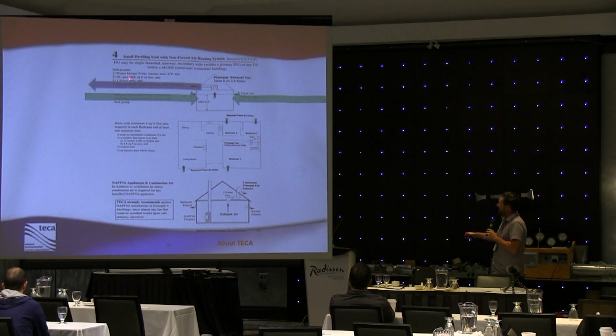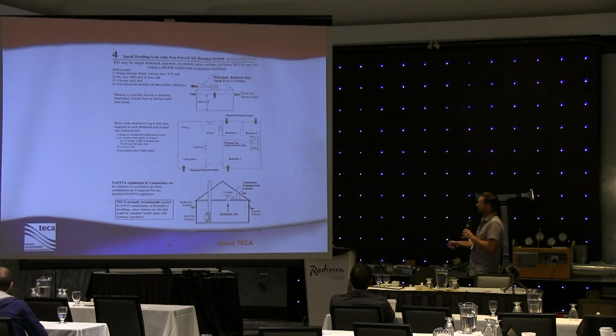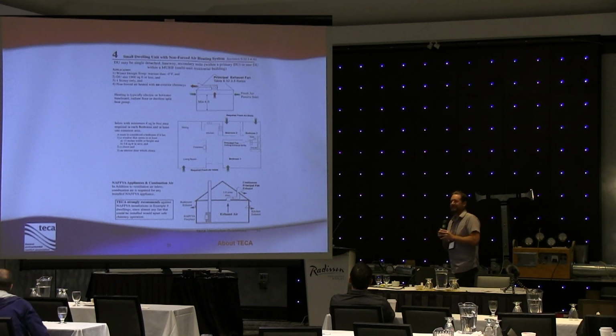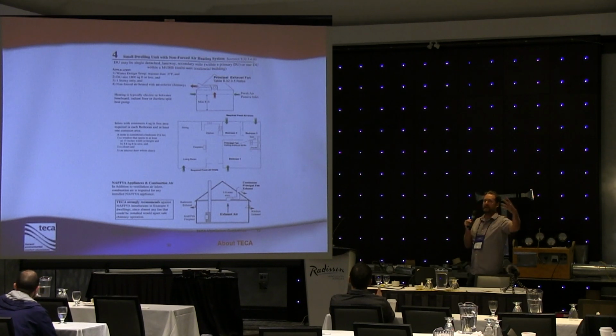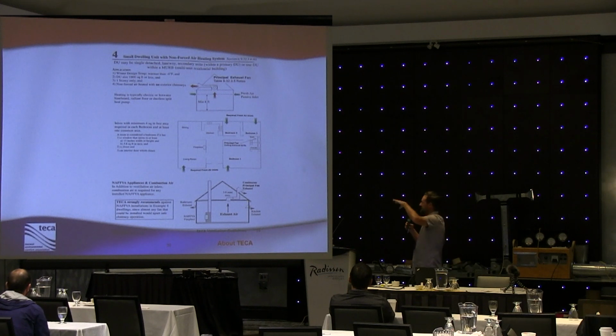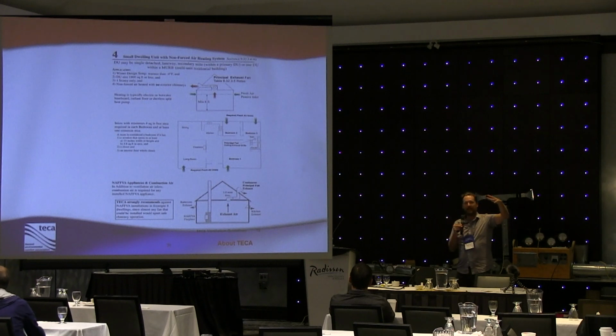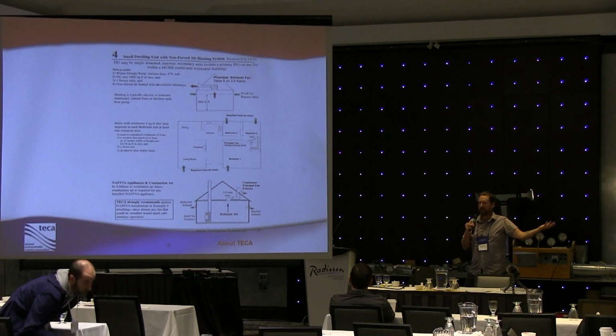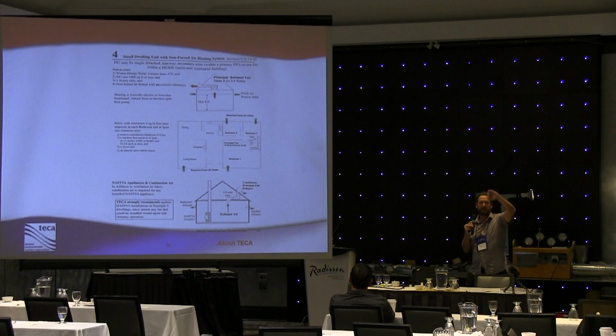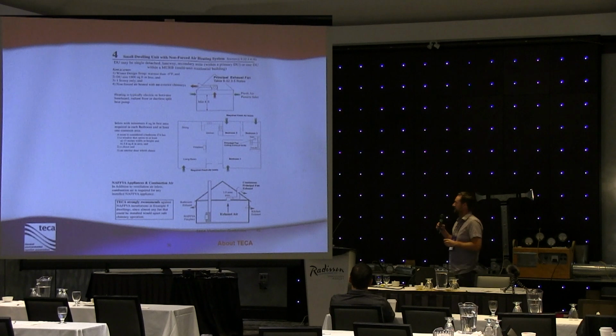Another criteria is that we have it set up to be on 1,800 square feet or less and on one story. Well, if we get too large of a building, we may get other things happening where one vent may start to allow air to flow out of it rather than fresh air come in. We get too large of a residence. Or if we have multiple stories, if we put this type of system in a 2-story building and we have vents on both stories, what's going to happen then? The vents on the lower stories are going to be bringing fresh air in, and the vents on the upper stories are going to allow that air to migrate to the outside. So it will definitely contravene the intention of the system.